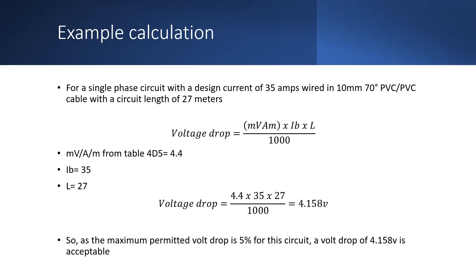So here we have an example calculation for a single phase circuit with a design current of 35 amps wired in 10mm 70 degree PVC-PVC cable with a circuit length of 27 meters. So the value for millivolts per ampere per meter is taken in this instance from table 4D5 and that is 4.4.